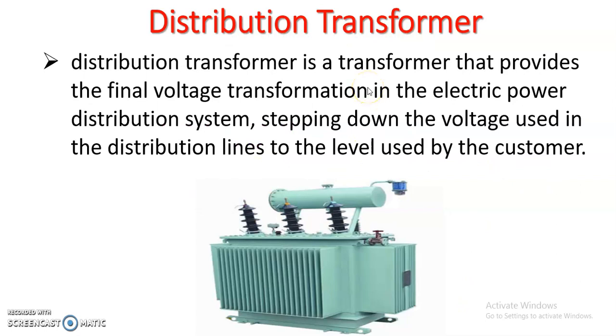Then next important equipment is distribution transformer. So in case of distribution transformer, in case of your plinth mounted substation, it can be rated up to 200 kVA to 1000 kVA. So it is a heavier transformer. It works similarly. Incoming, that is HV winding voltage is 11 kV and LV voltage is 400 or 440 volt.